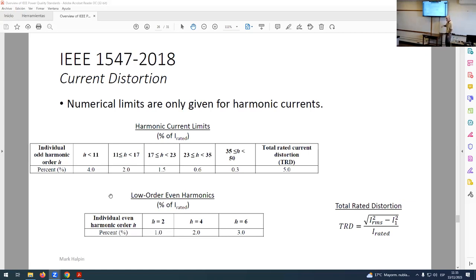All right, another thing. Does a PWM inverter, under ideal conditions, produce fifth harmonic? No, not at all. PWM inverters produce harmonics at really high frequencies. That's one of their big advantages. So I'm going to hook an inverter to the power system. It's going to produce a lot of harmonic distortion, but it's at high frequencies, potentially way above the 50th. What am I going to do about that?